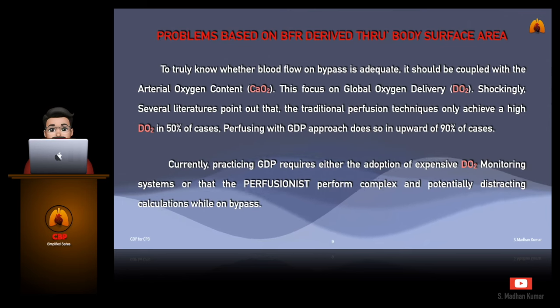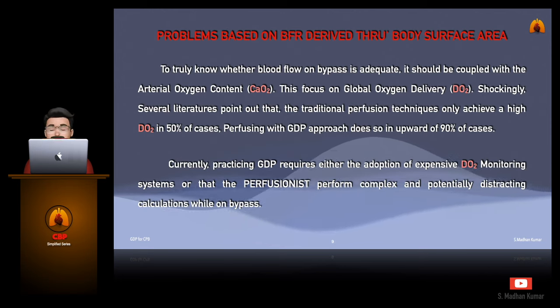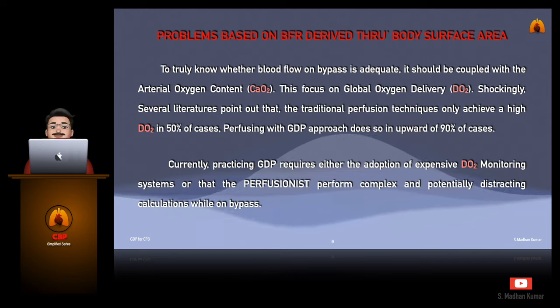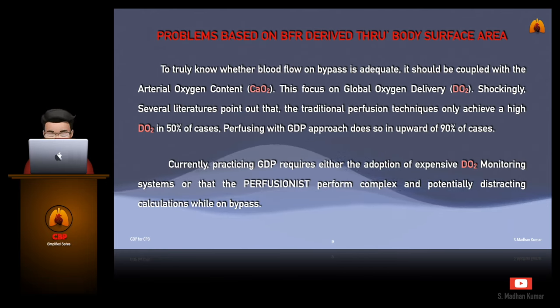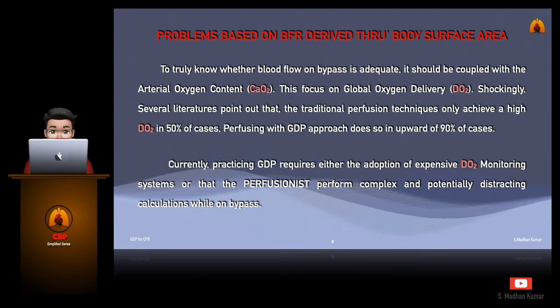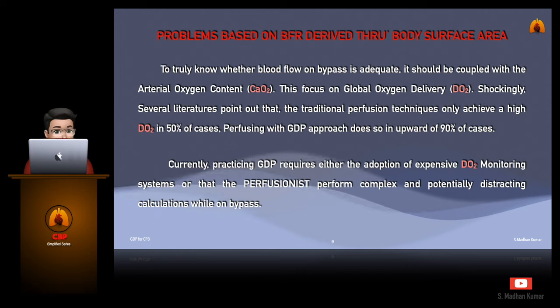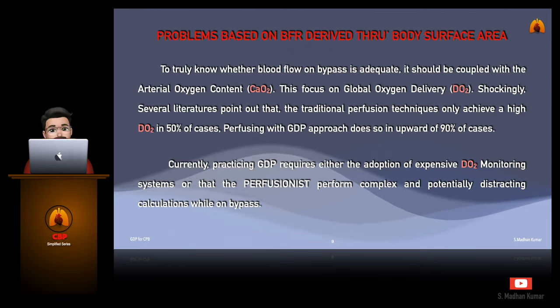To truly know whether blood flow on bypass is adequate, it should be coupled with the arterial oxygen content, otherwise called as CaO2. This focuses on global oxygen delivery, which is the DO2. Shockingly, several literatures pointed out that traditional perfusion techniques only achieve a high DO2 in 50% of cases. Perfusing with a goal-directed perfusion approach does so in upward of 90% of cases. Currently, practicing goal-directed perfusion requires either the adoption of expensive DO2 monitoring systems or that the perfusionist perform complex and potentially distracting calculations while on bypass.